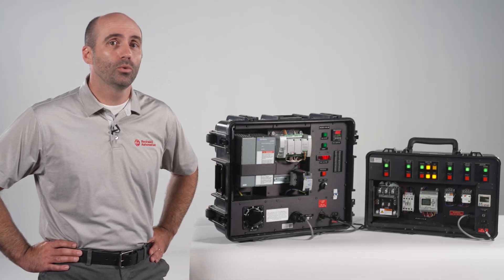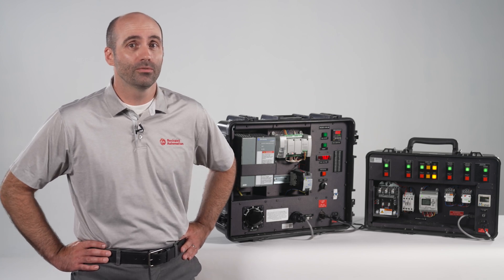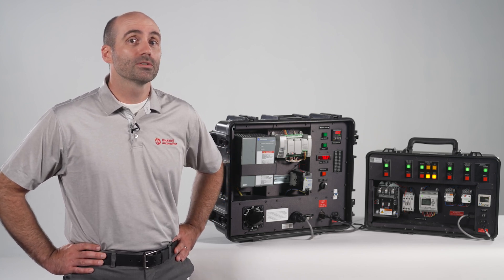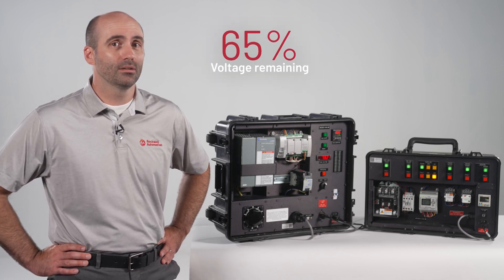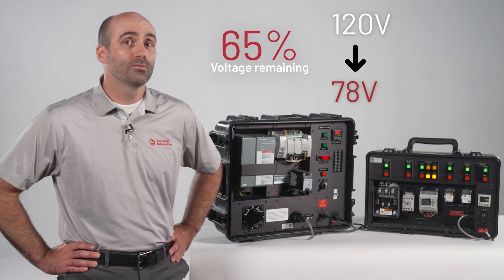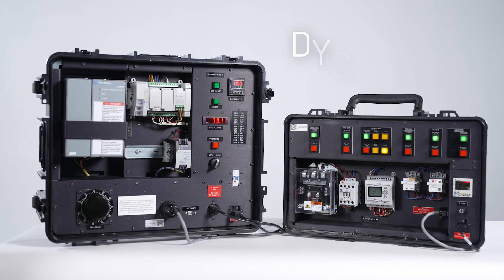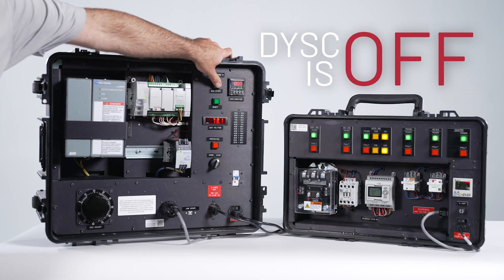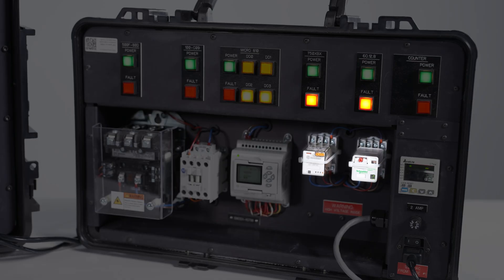The first set of tests we'll do without the DySC voltage sag corrector in circuit, to test the robustness of these loads to voltage sags. In our first test, we'll simulate a voltage sag with 65% voltage remaining — 78 volts on our 120 volt nominal line. This voltage sag will last for only 100 milliseconds. Let's run the first simulation. We can see that about a third of our on-site equipment tripped.